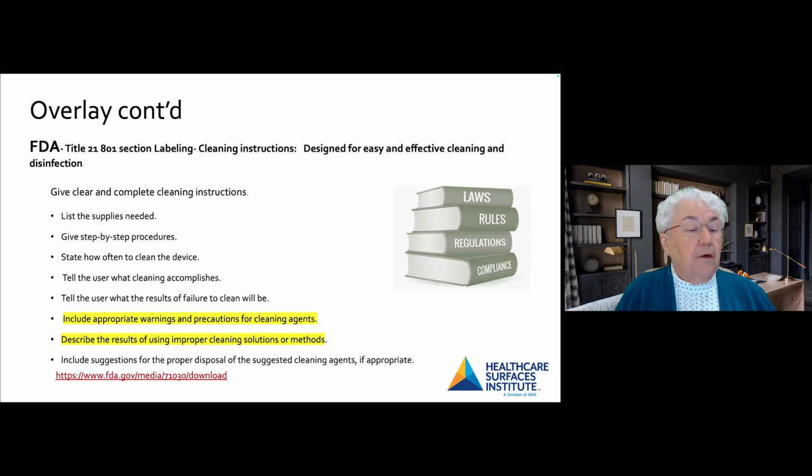And highlighted here are appropriate warnings and precautions for cleaning agents, such as if they pool where they might be connected or around corners, that might damage the actual device. And then describe the results of using improper cleaning solutions or methods.